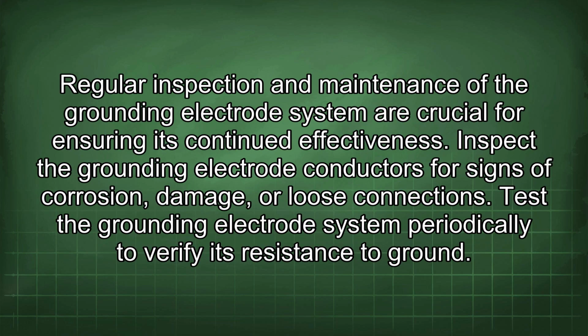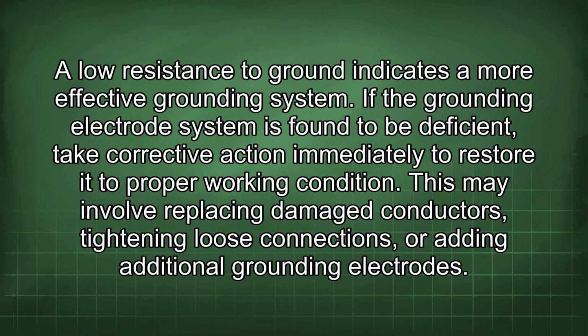Regular inspection and maintenance of the grounding electrode system are crucial for ensuring its continued effectiveness. Inspect the grounding electrode conductors for signs of corrosion, damage, or loose connections. Test the grounding electrode system periodically to verify its resistance to ground. A low resistance to ground indicates a more effective grounding system. If the grounding electrode system is found to be deficient, take corrective action immediately to restore it to proper working condition. This may involve replacing damaged conductors, tightening loose connections, or adding additional grounding electrodes.